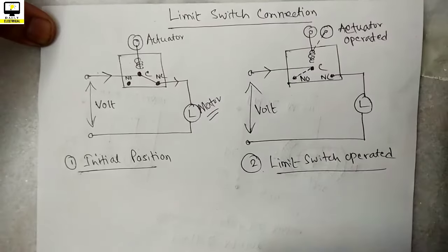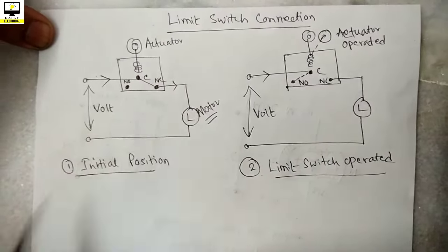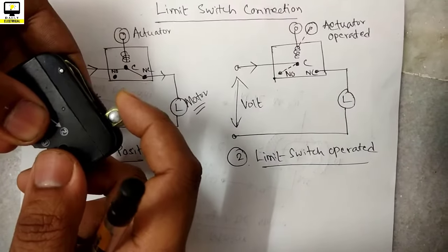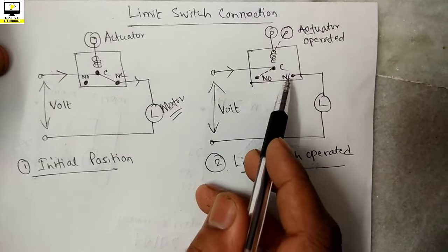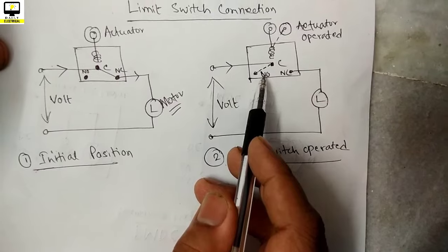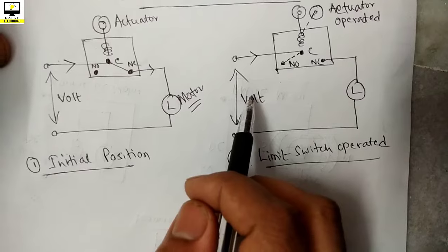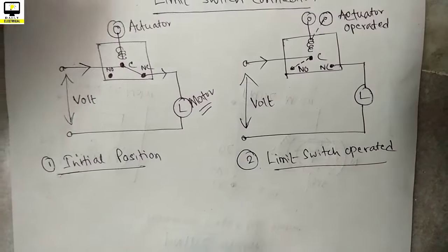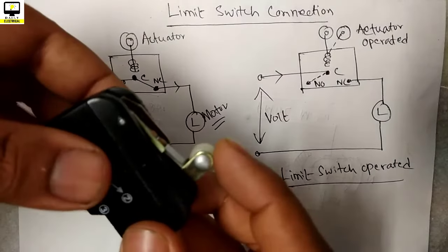But whenever in the second position limit switch is operated, that means this actuator has been shifted by a pressure of any moving object, then the voltage you have provided to the common connection cannot go to the NC connection because the potential free contacts has been changed to NO. Then the series circuit is broken and the load is disconnected from the supply. In this way, using a limit switch you can connect or disconnect a supply from the load by operating the limit switch head.